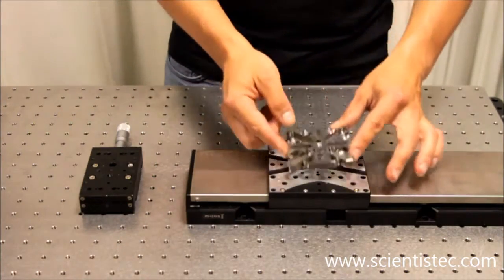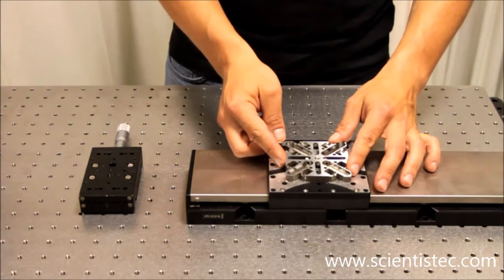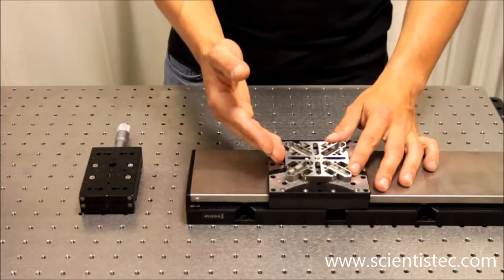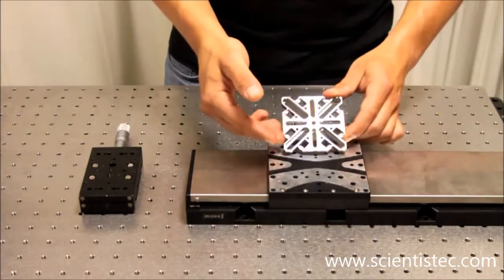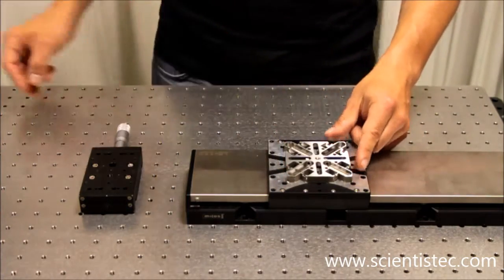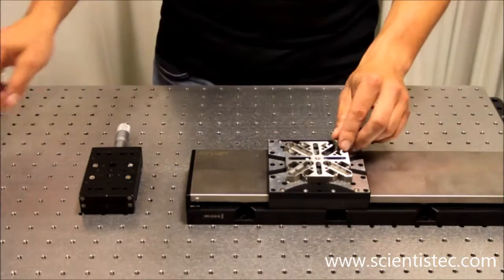To do so, I place the adapter on top of the MICOS stage. Now one can see how the adapter can be bolted on the platform with the M6 screws directly. In this combination no washers are required.